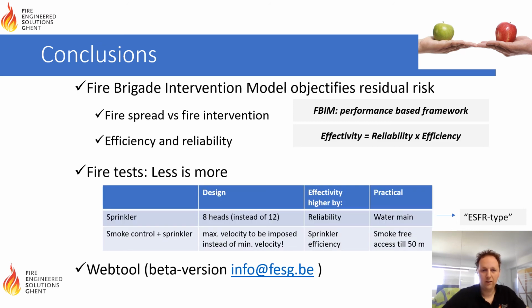For sprinkler design, what we've seen is that designing based on 8 heads instead of 12 would allow you to connect the sprinkler to the water main, especially in residential buildings. That could be a big impact on the reliability. So increased reliability by a more simple system could be positive for the total effectivity.